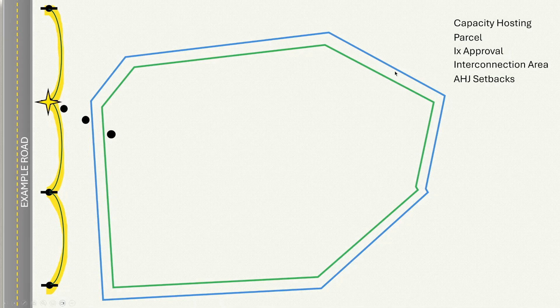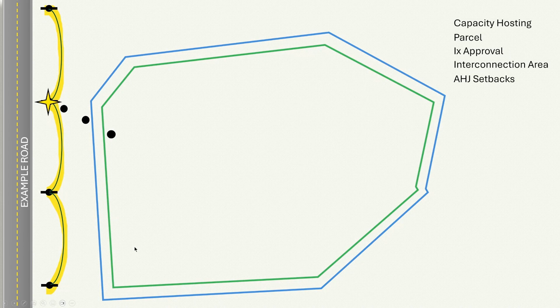In this graphic we're trying to identify exactly how much capacity we could put on the site based on a fixed parcel boundary. The first thing we want to do is look at the AHJ setbacks. This is typically found in the zoning ordinances, which might say you need a 50 foot setback from the parcel line, or maybe 100 foot, or maybe it's 500 feet from the road, which will vary from municipality to municipality.